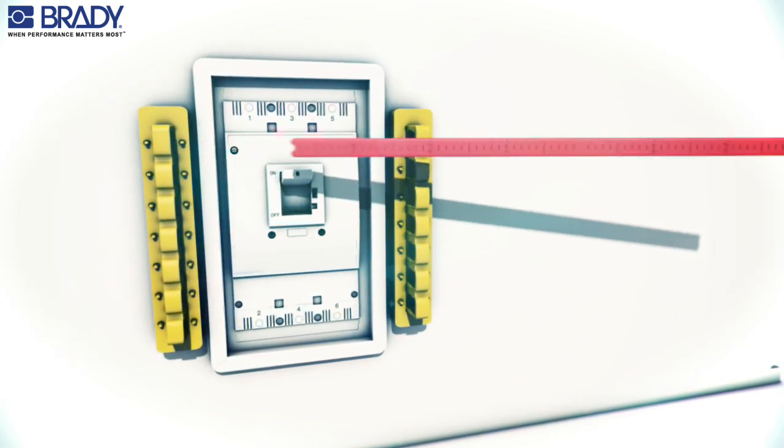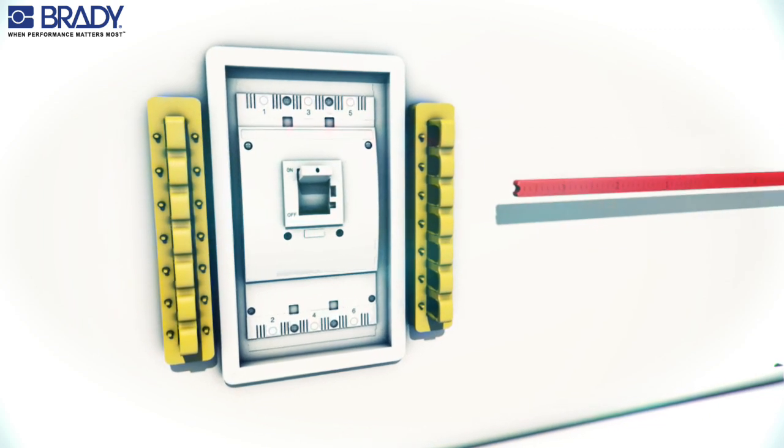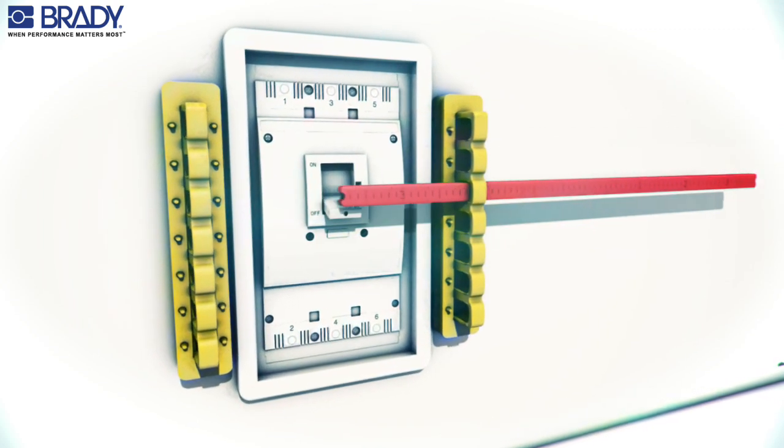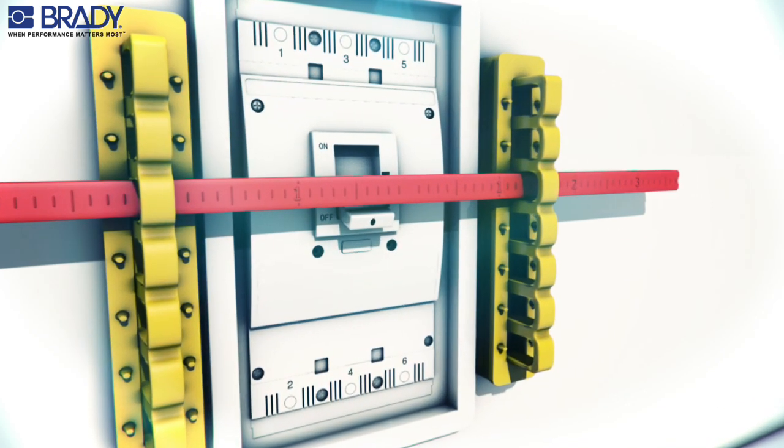The red bar is used to lock the switch in the off position during lockout or tagout applications. Position the red bar through the yellow mounting rails and against the switch when it is in the off position. Verify that the switch cannot be thrown.